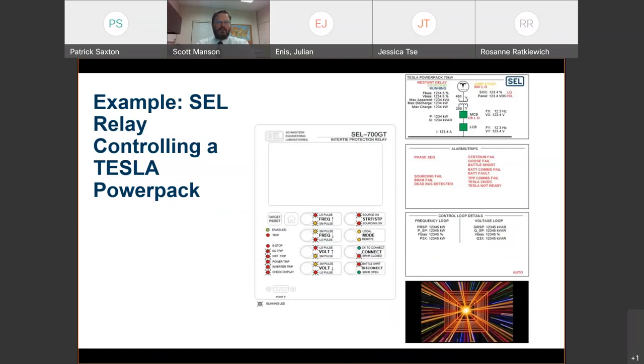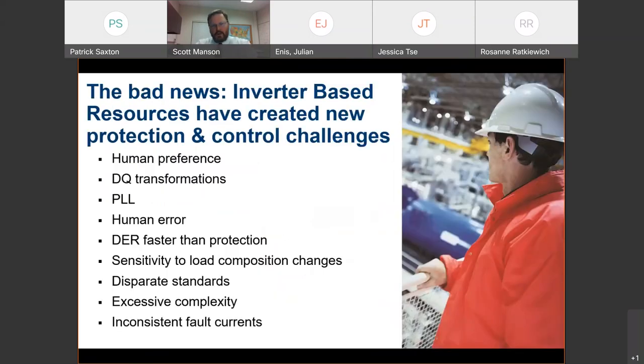Turns out, if you wish to have a stable, reliable, resilient grid, the simplest thing you can do is have your protective relays take control of your inverters. You do that and you solve a lot of problems, and I'll show you many here in a few minutes. So inverter-based resources go by many names. If you have a photovoltaic system, you have an inverter. If you have a wind turbine system, type 4, you have an inverter. If you have a battery system, you have an inverter. The modern energy and renewable energy industries depend on inverters to take energy at DC and convert it to AC, direct current to alternating current.